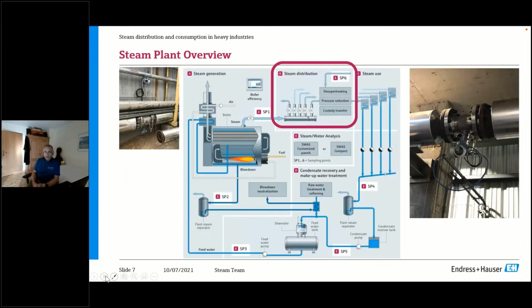So we are now on the distribution side. Typically you have a steam main header, and from this you distribute to the different points of end use. And you may or may not have the superheating. For instance, if you're taking steam from a higher pressure side, in chemical plants or in larger petrochemical sites, you have steam for power generation, and from that you get lower pressure steam, so 20 bar typically. And from that, you then reduce even further. If you want to heat some heat exchangers, then you're talking about lower temperatures and pressures.